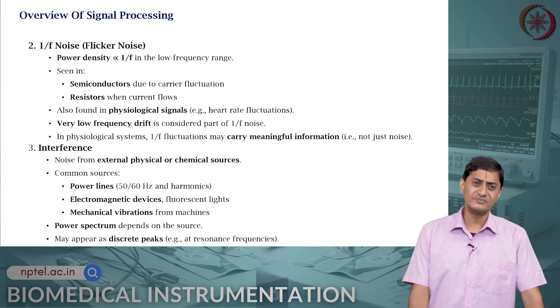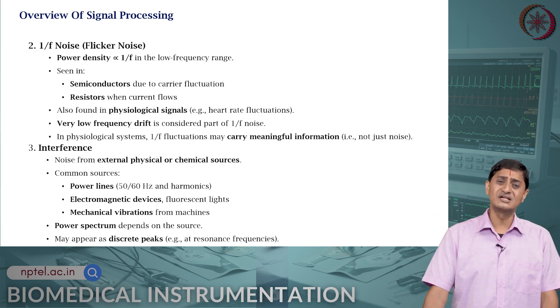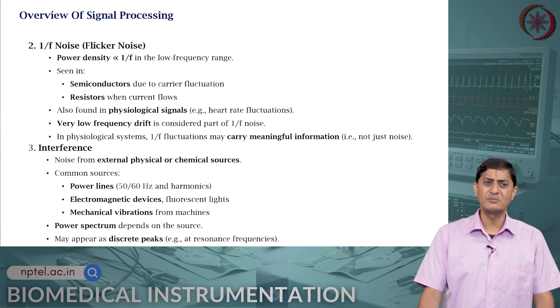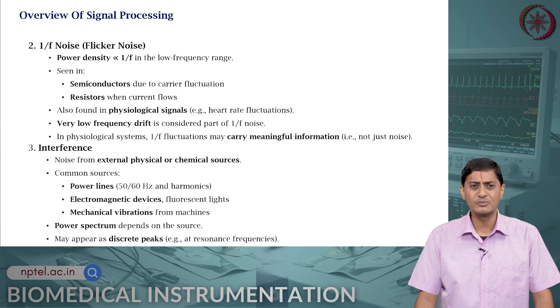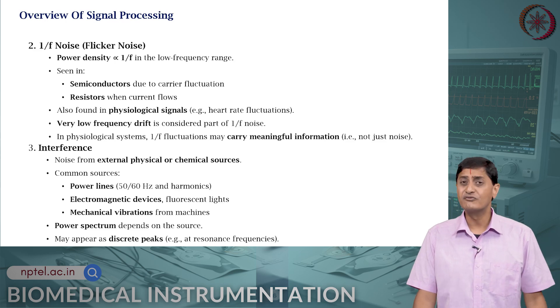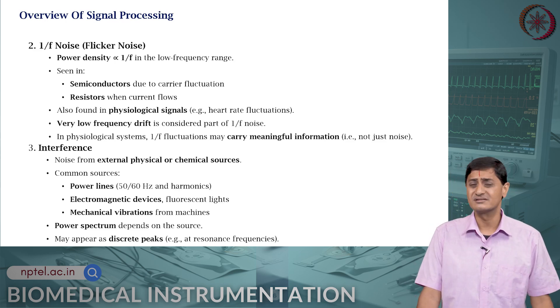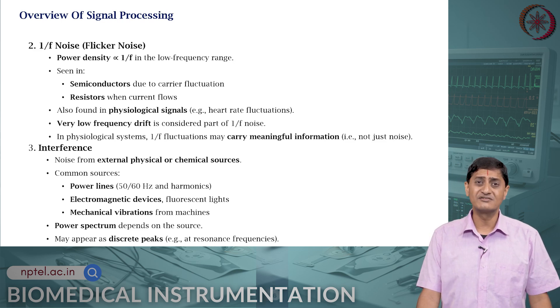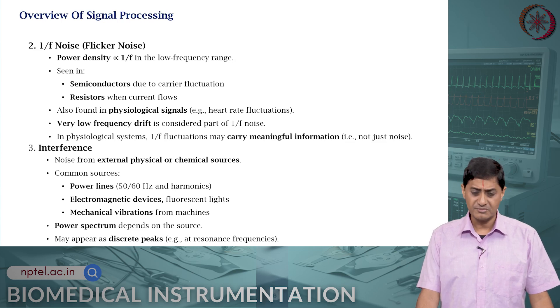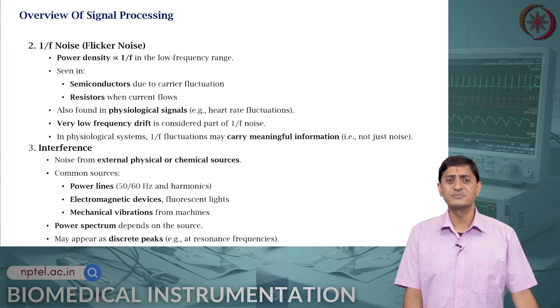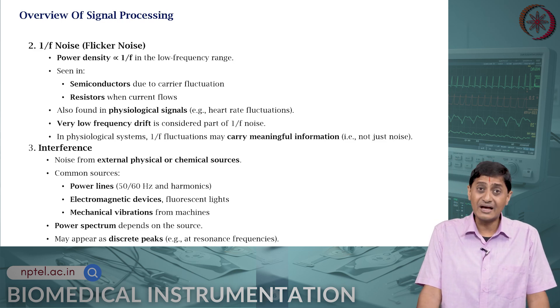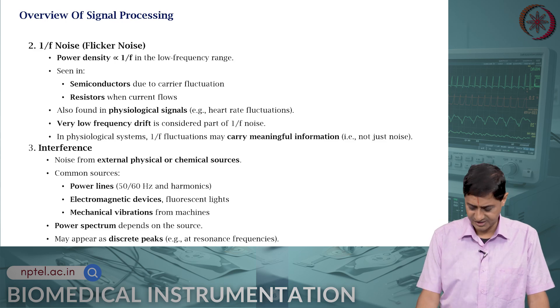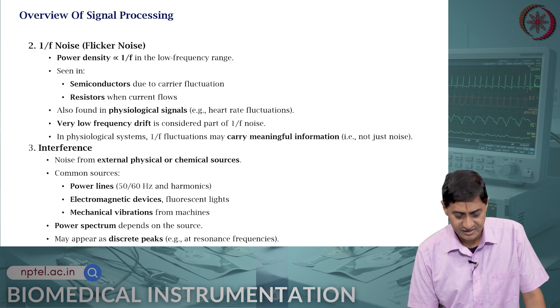Then there is interference — noise from external physical or chemical sources. Common sources are power line noise, electromagnetic devices such as fluorescent lights or other large electronic devices, and mechanical vibrations from nearby machines. The nature of the power spectrum depends on the source of the noise, and it might appear as discrete peaks, for example at resonant frequencies or their harmonics.